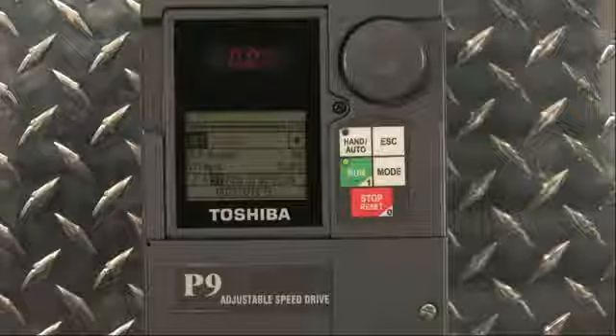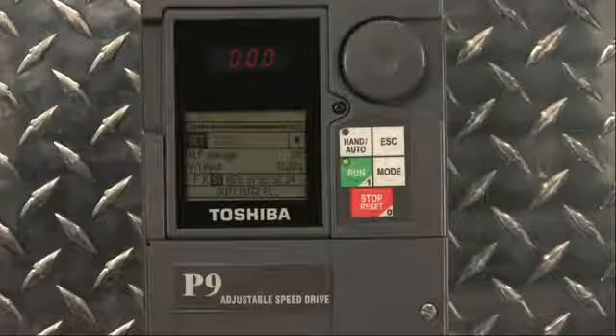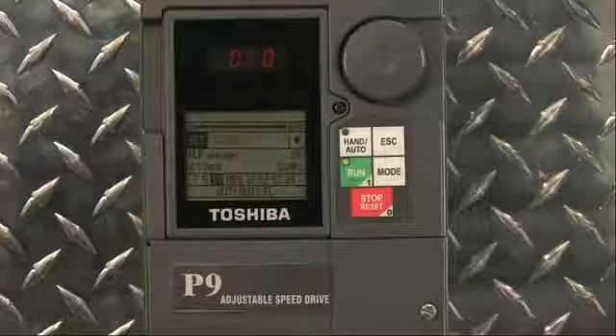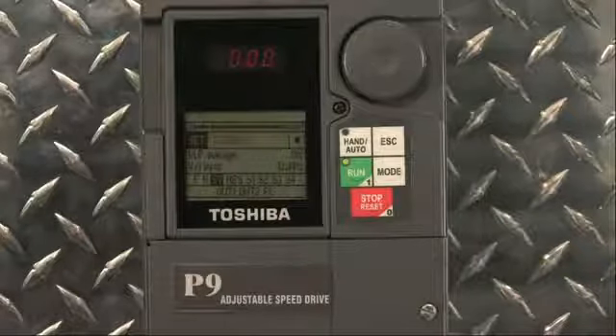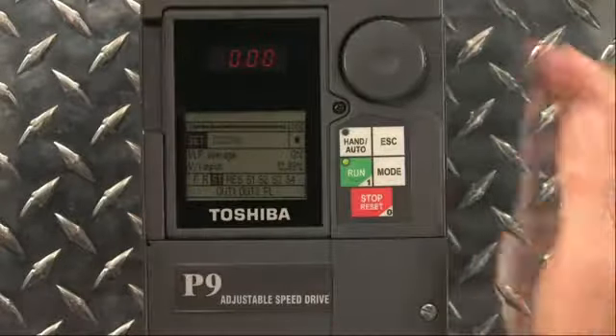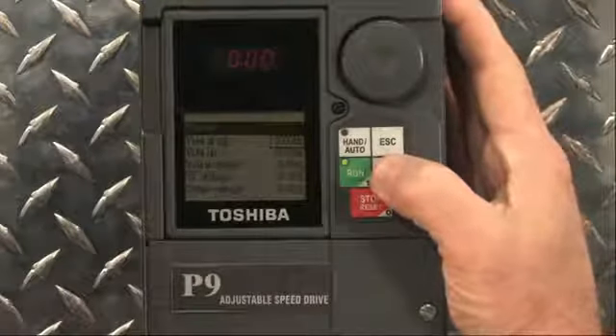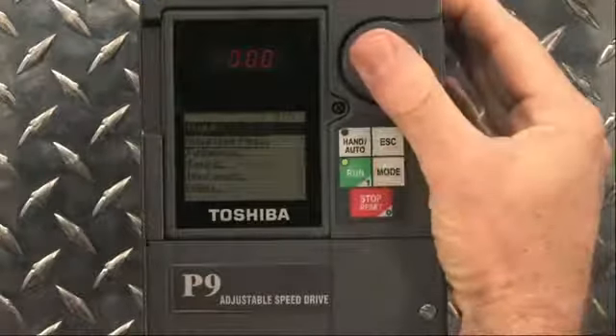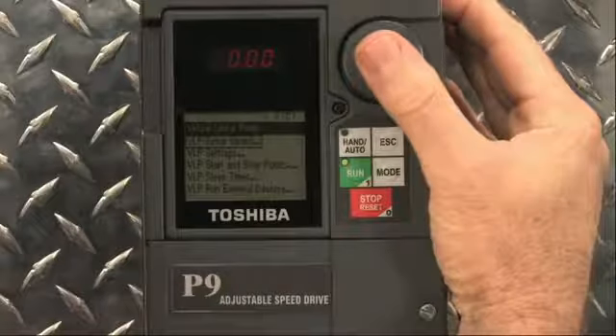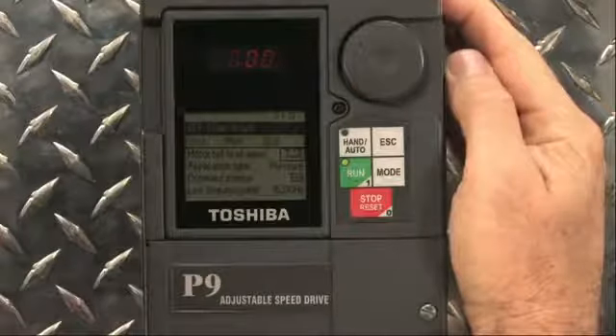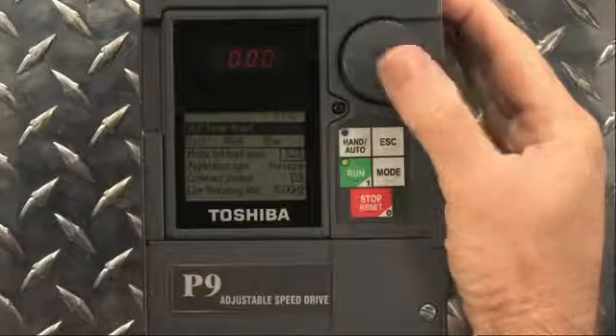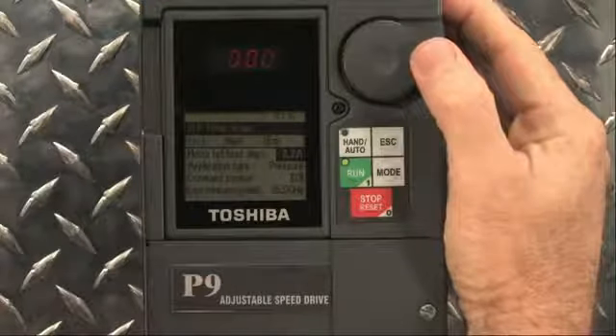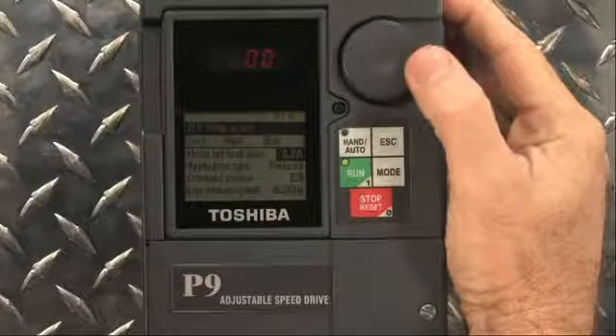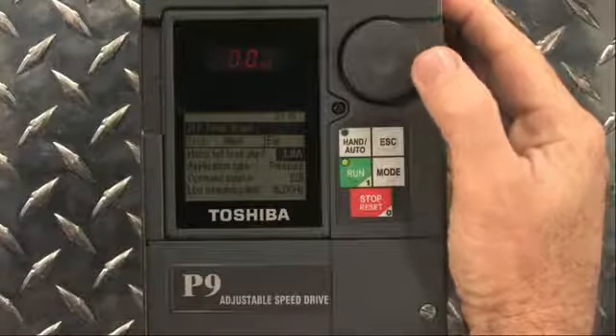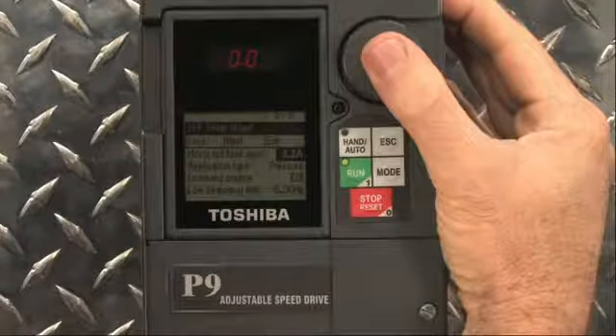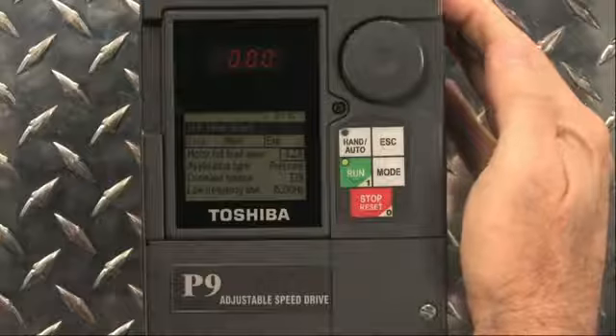Setup Wizard. The Toshiba P9 Setup Wizard makes it so easy to completely set up your drive in just a few simple steps. Let's give it a try. Once in the program menu, select Virtual Linear Pump submenu and press Enter. Selecting VLP Setup Wizard opens the first system description screen where the P9 will ask for the full load amps rating of the motor. This rating can be found on the motor's nameplate. This P9 pump demonstrator uses motors with a full load amps rating of 3.2 amps, which is entered here.